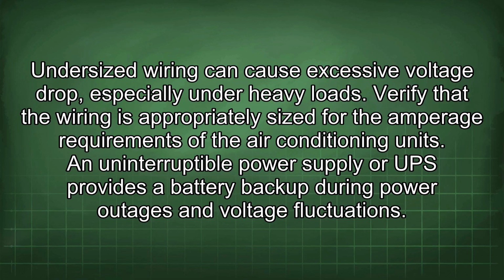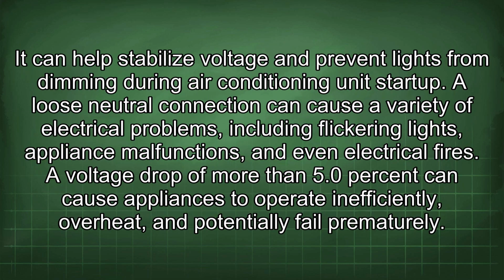An uninterruptible power supply or UPS provides a battery backup during power outages and voltage fluctuations. It can help stabilize voltage and prevent lights from dimming during air conditioning unit startup. A loose neutral connection can cause a variety of electrical problems, including flickering lights, appliance malfunctions, and even electrical fires. A voltage drop of more than 5.0% can cause appliances to operate inefficiently, overheat, and potentially fail prematurely.